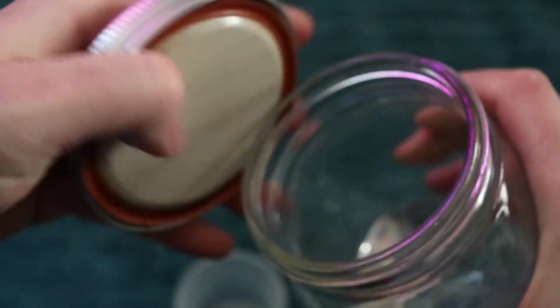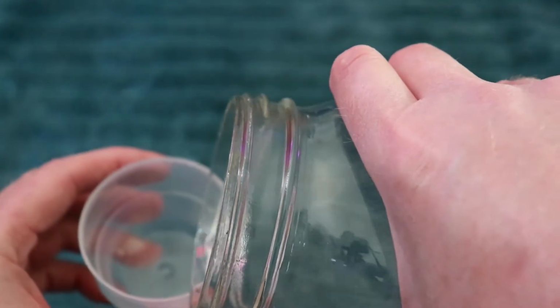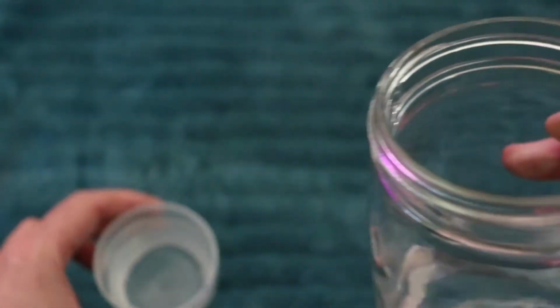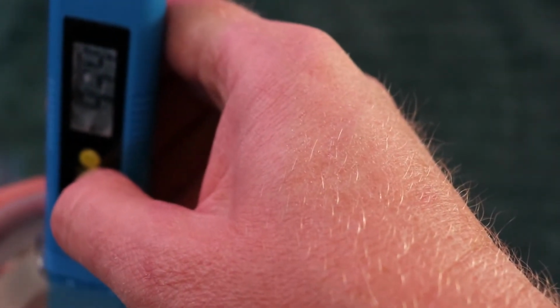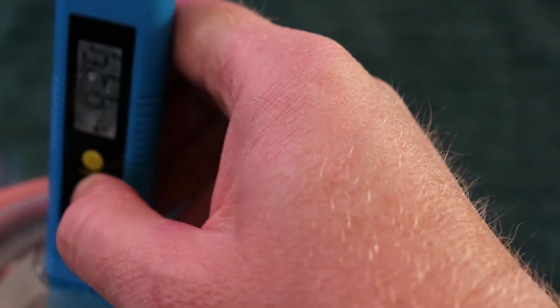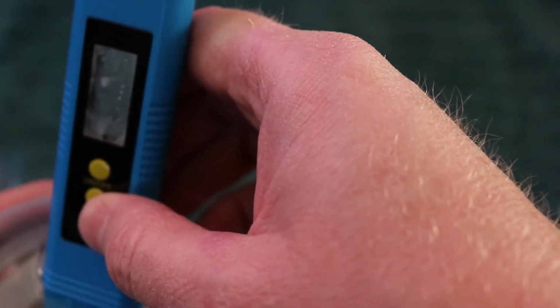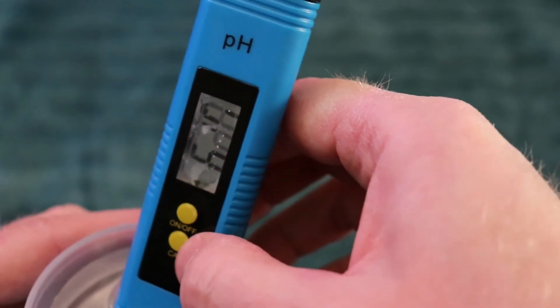Then to calibrate this, I have a 6.86 pH solution in a sealed canning jar, and this is how I store it, on a dark shelf, not near any heat source or any light, so nothing should be tampering with the pH on this. And shake it up just to make sure everything in there is dissolved. Stir it up, fill it up. Press and hold the cal button for 5 seconds. Release it, it'll flash 686, and when it blinks 3 times, then you know it is calibrated for 6.86 pH.